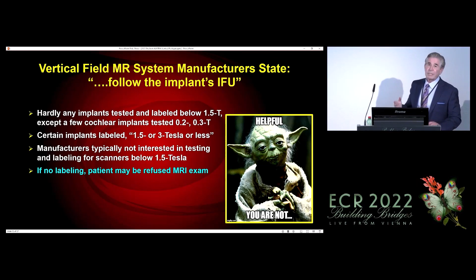And in fact, if you look at the instructions for use for those implants that state 1.5 or 3 Tesla or less, it may also state horizontal bore scanners only. So the manufacturers, as I indicated, and I've approached them, are not really interested in getting testing and labeling done for vertical bore scanners with respect to their implants. And as a result of that, there are many MRI facilities, and I know many of them in the US and in Canada and elsewhere, where if they don't have specific labeling for the implant or device, you're not allowed to scan that patient, and they refuse the MRI exam on a vertical bore scanner, which is terrible because it doesn't afford the possibility of being able to scan obese individuals and other patients who may benefit from exams on vertical bore scanners.